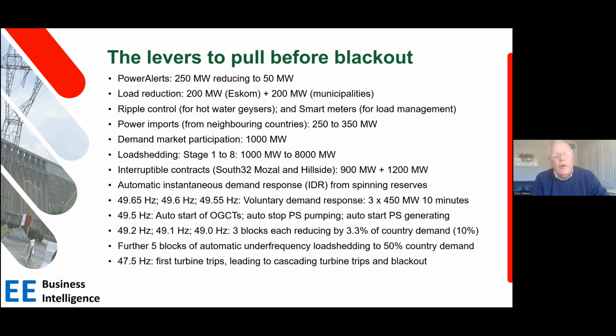At a certain frequency, a certain amount of load will be automatically kicked off the system. And they have all these different levels. Even when the frequency is dropping fast, in other words, the rate of change of frequency is fast, it responds even quicker, shedding load. So there's a whole lot of levels of automatic load shedding, which can, in the end, interrupt a massive part of the South African demand.